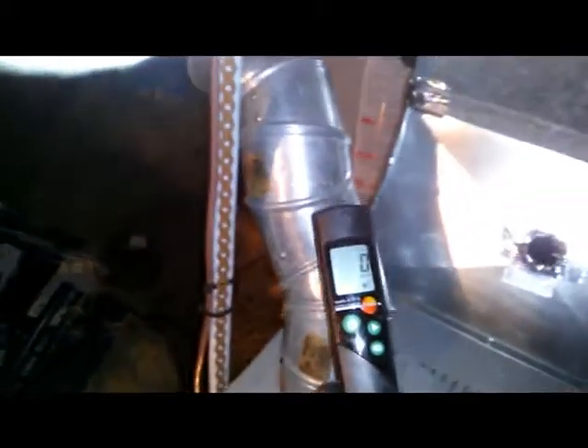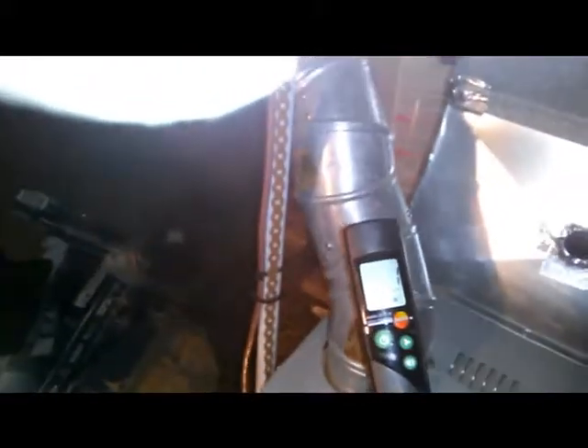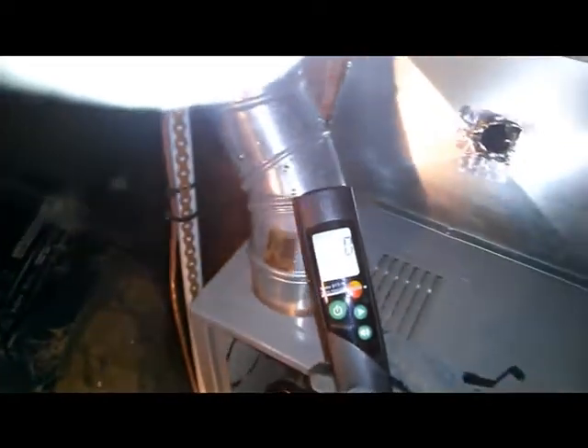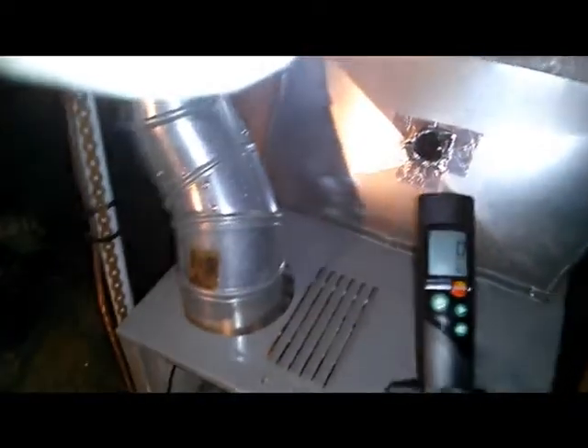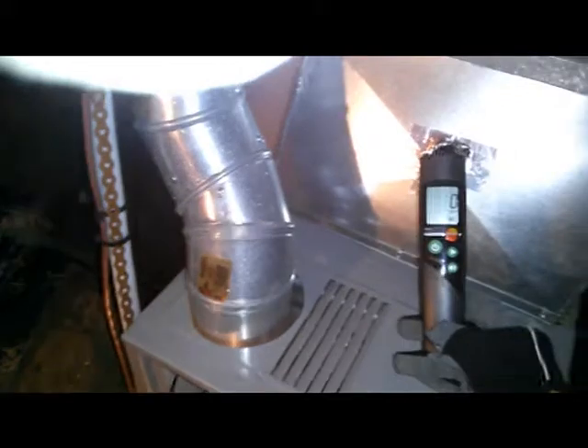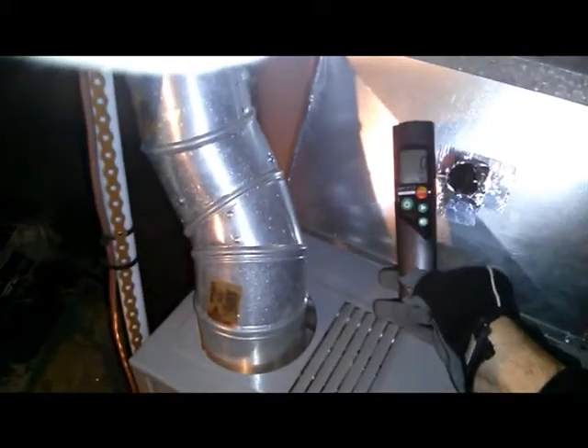Got good flames. I'm just going to take a look at my carbon monoxide reading, checking the venting, making sure nothing's leaking from the exhaust, from the venting, which seems to be doing fine. I actually find more problems with venting issues causing carbon monoxide than I ever have with it leaking from the plenum. So I'm just going to put this over here.